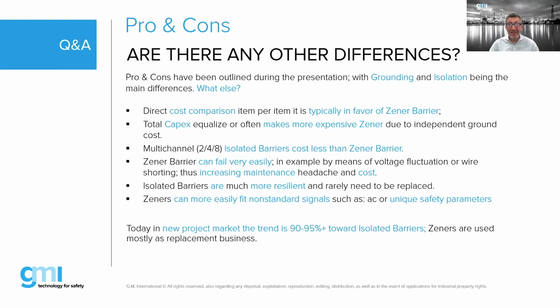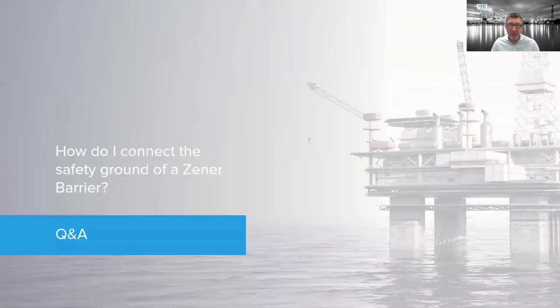To be 100% honest, there is also a limit on the barrier. An isolated barrier has a certain parameter, which is the maximum voltage you can apply to that device. In the case of GMI, they're all 250 volts. So it means the power supply you're powering into an IS barrier shall not be bigger than 250 volts. Of course, it's 24 volts, but yes, there are some limits. Okay, let's move forward. We have some prepared questions, and then we'll look.